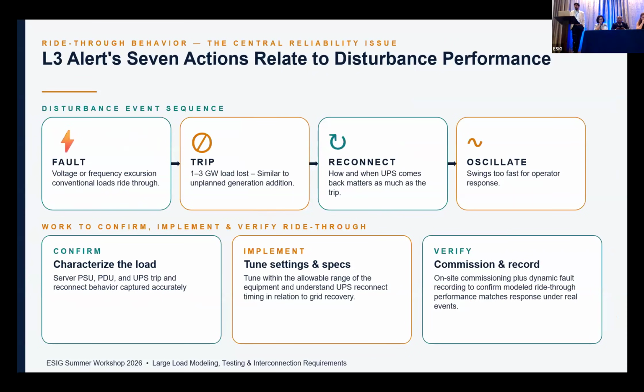A fault happens, you have voltage or frequency excursions. In the past, a lot of these larger loads were able to handle these or stay connected on the grid. But for data centers, the primary driver is to keep their equipment safe and continue to operate. They have on-site generation and backup generation, so the tendency in the past used to be to just back off if something happens. Now that's changing, where we have to be good grid citizens and better understand the reliability needs of the grid. That's why you've got to work with the UPS manufacturers and other OEMs to figure out how to meet some of these requirements.